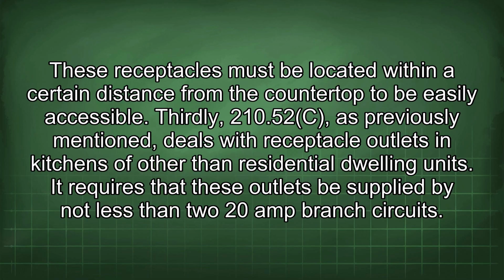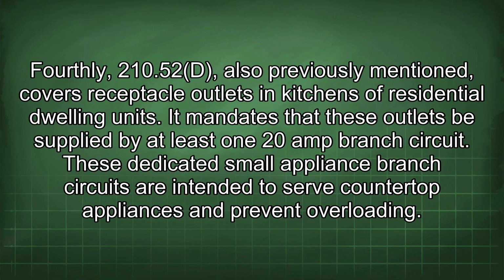210.52c, as previously mentioned, deals with receptacle outlets in kitchens of other than residential dwelling units. It requires that these outlets be supplied by not less than two 20-amp branch circuits. Fourthly, 210.52d, also previously mentioned, covers receptacle outlets in kitchens of residential dwelling units. It mandates that these outlets be supplied by at least one 20-amp branch circuit. These dedicated small appliance branch circuits are intended to serve countertop appliances and prevent overloading.